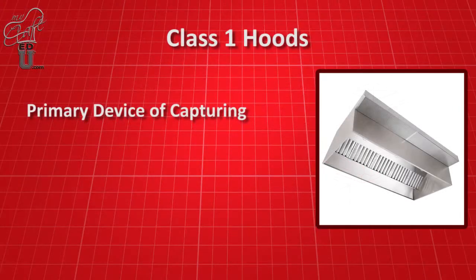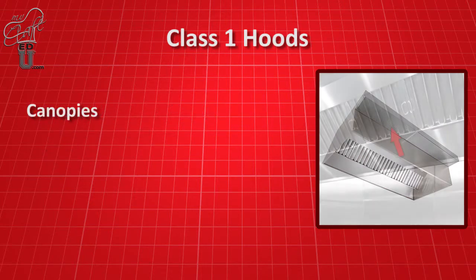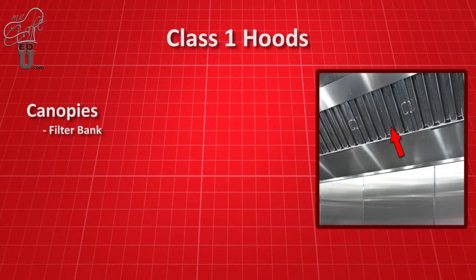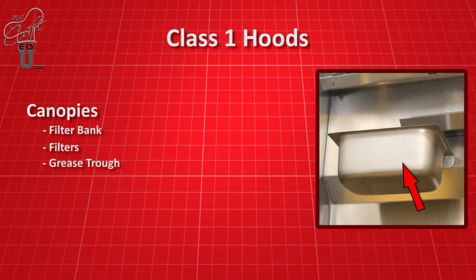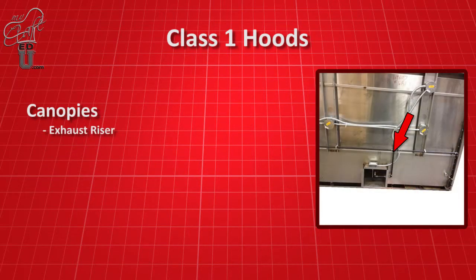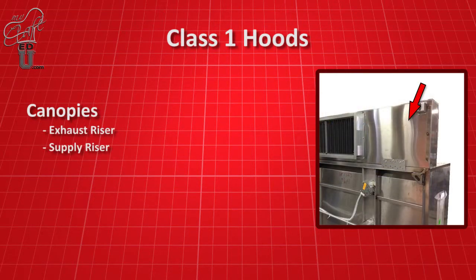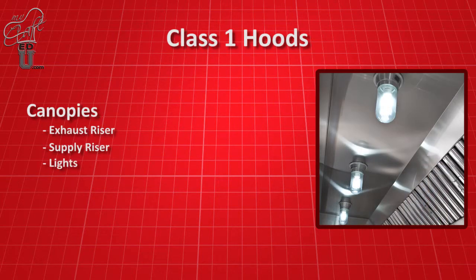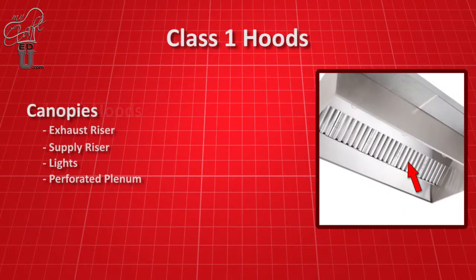Class 1 exhaust hoods, or canopies, are the primary device for capturing the grease-laden vapor, heat, and smoke that emits from the cooking equipment. Canopies are comprised of a filter bank, filters, grease trough, grease cup, exhaust riser, supply riser, lights, and make-up air perforated plenum.